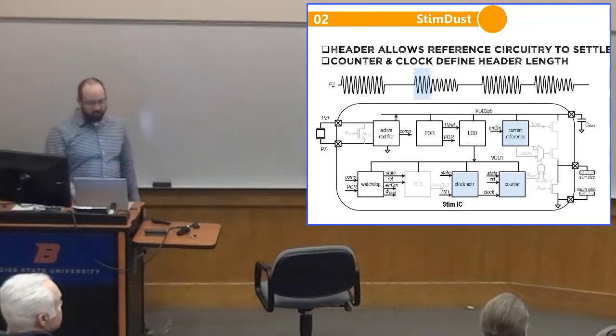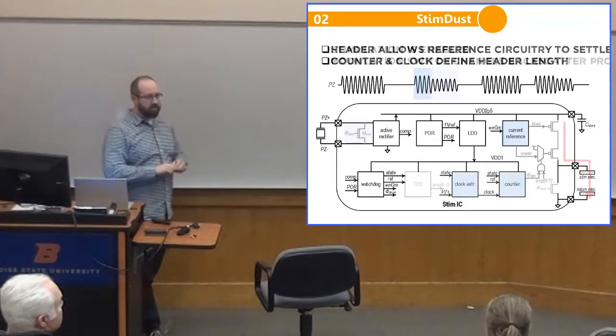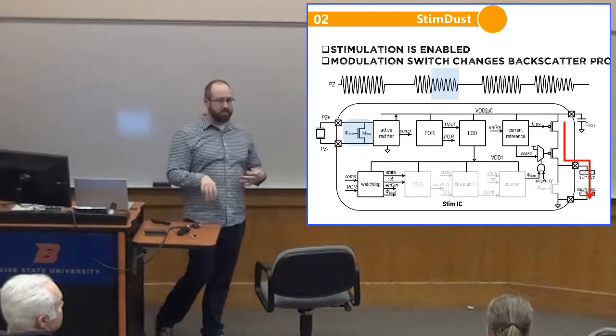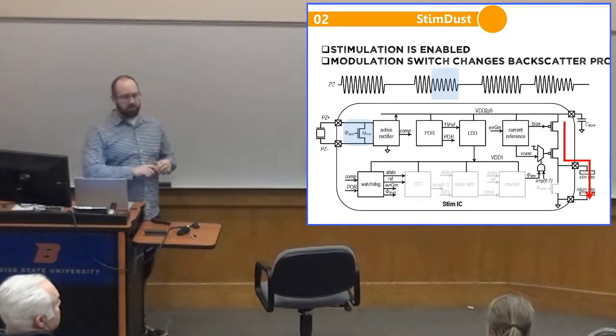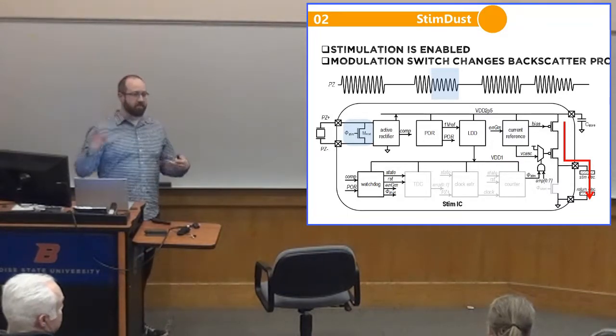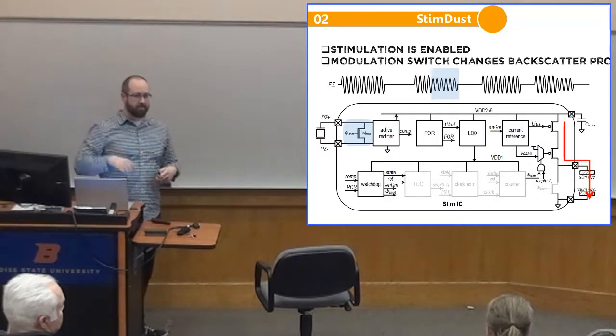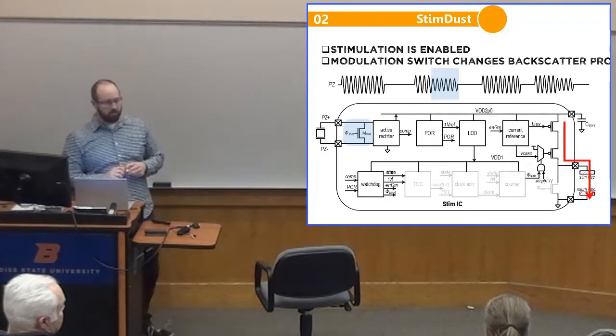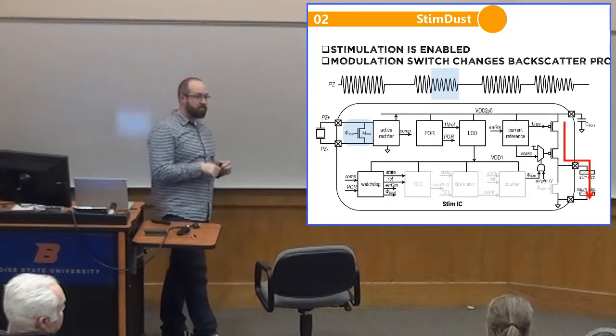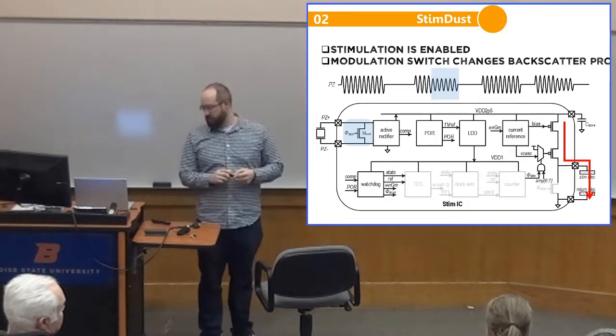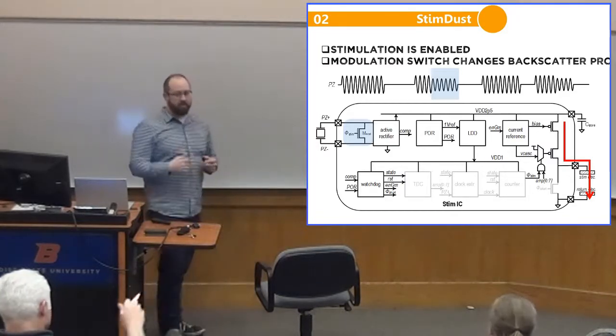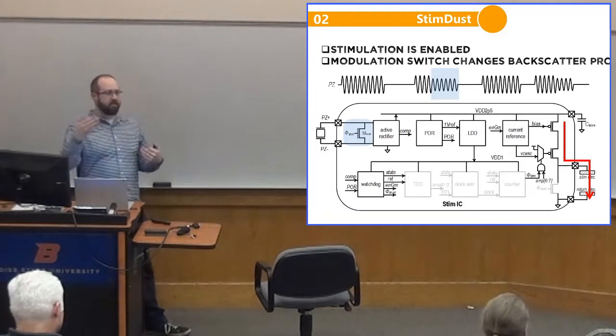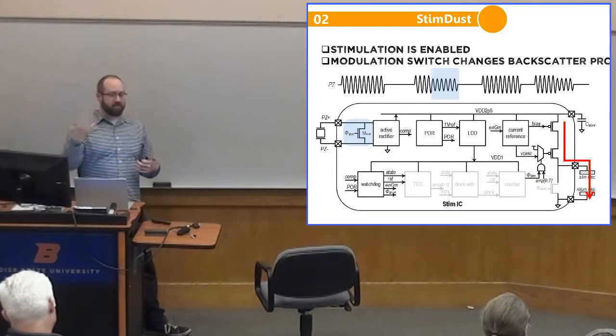So that turns on, everything settles, and then in this next bit we actually start to stimulate. We program an amplitude, which sets the amount of current that goes from our stimulation electrode to our sink. There's also a switch on the piezo terminal, which I'll talk about a few slides from now, that will modulate the backscatter and tell the external system that we're stimulating.